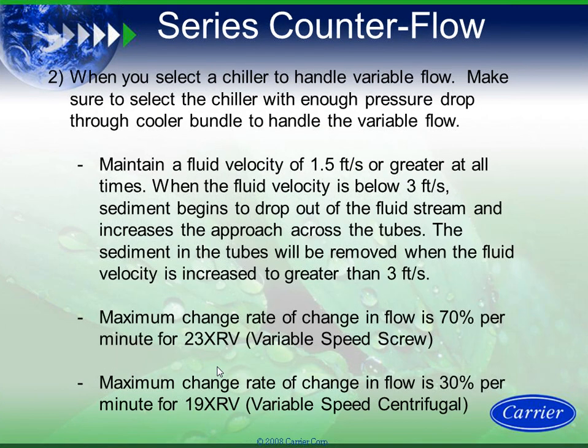Okay, so when we select chillers to handle variable primary flow, we need to maintain a minimum of 1.5 feet per second or greater at all times in the cooler. So that's basically one of the criteria on minimum flows on a series counterflow variable primary flow system, which is very low flows on there.